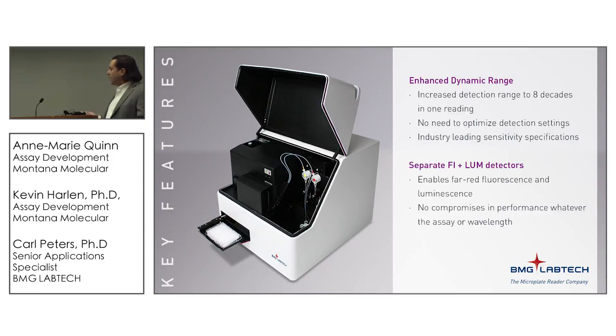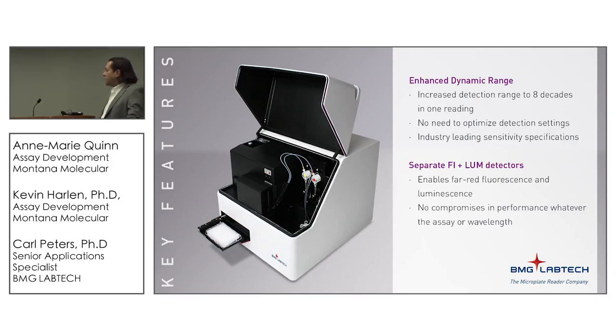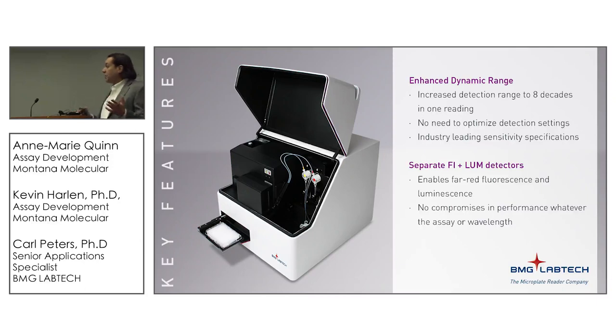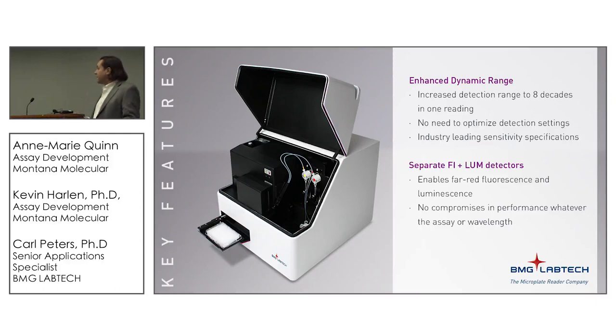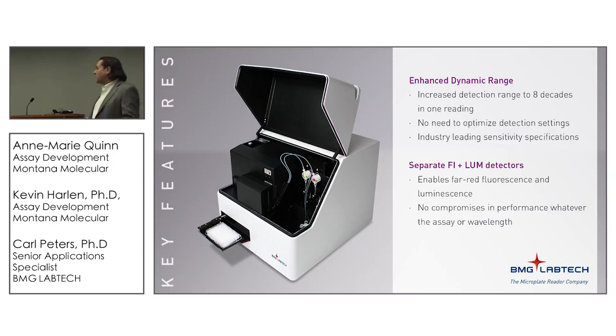Another important aspect for people doing multiplexed assays is improved far-red fluorescence detection. The ClarioStar Plus can read fluorescence up to 900 nanometers, allowing better separation of signals and opening the doors to any fluorescent tool available. Additionally, if you have a scenario requiring it, there's a second PMT dedicated for luminescence and AlphaScreen detection — really providing the absolute best tools for each individual assay.